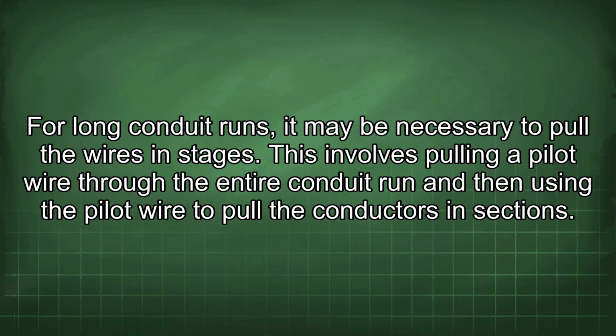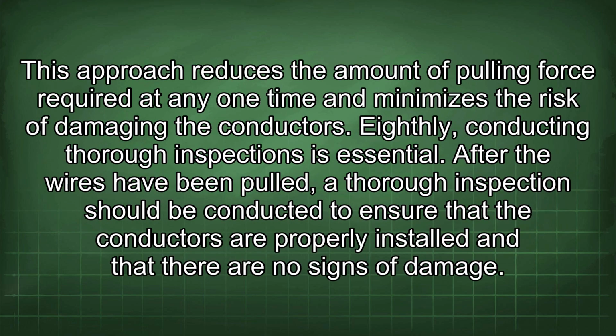For long conduit runs, it may be necessary to pull the wires in stages. This involves pulling a pilot wire through the entire conduit run and then using the pilot wire to pull the conductors in sections. This approach reduces the amount of pulling force required at any one time and minimizes the risk of damaging the conductors. Eighthly, conducting thorough inspections is essential. After the wires have been pulled, a thorough inspection should be conducted to ensure that the conductors are properly installed and that there are no signs of damage.